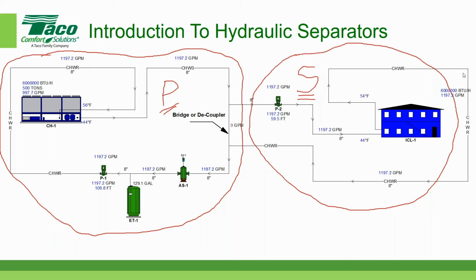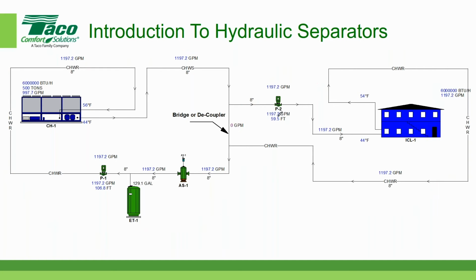Okay. Now, with a little luck, I'll be able to erase that. Look at that. And this device right here, or this part of the primary, secondary loop, is where the decoupler is. The most common terms are bridge, decoupler, or hydraulic separator. That's when we have a straight run of pipe, and then we have a tap to draw water off of that, and then a return line here. So let's look at a couple of different pumping scenarios.